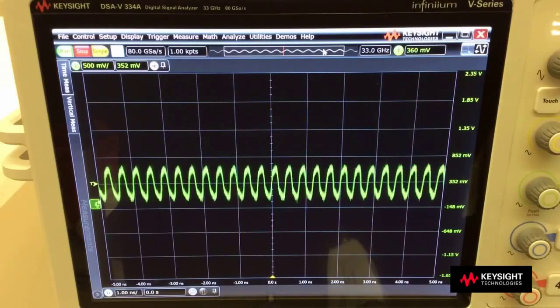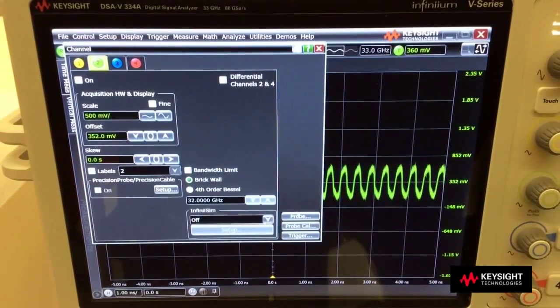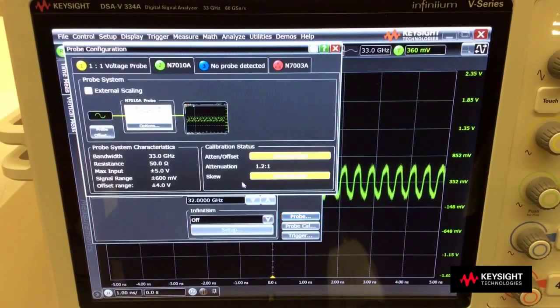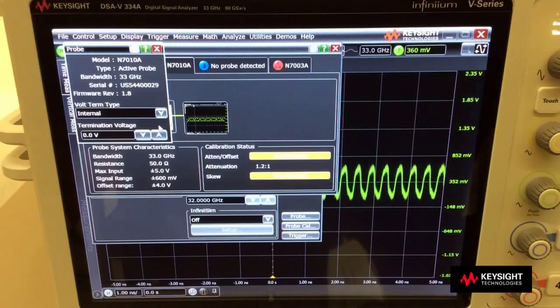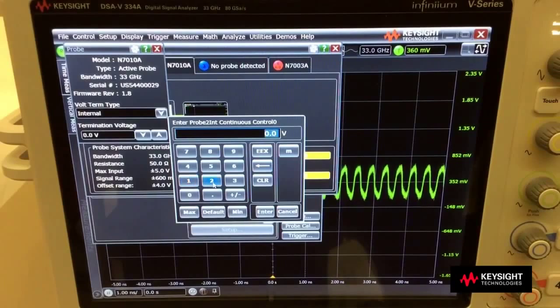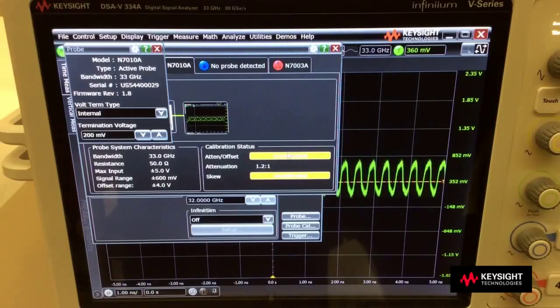Right now, I have the adapter attached to channel 2, and in order to change the termination voltage, I go into the channel menu, I select probe, and right here I can go into the probe option, and I can change the termination voltage. So assuming that I have an M-PHY signal and it needs to be terminated into 200 millivolts, I need to enter the 200 millivolts here, and then the 200 millivolts is now applied to the signal that I am measuring.